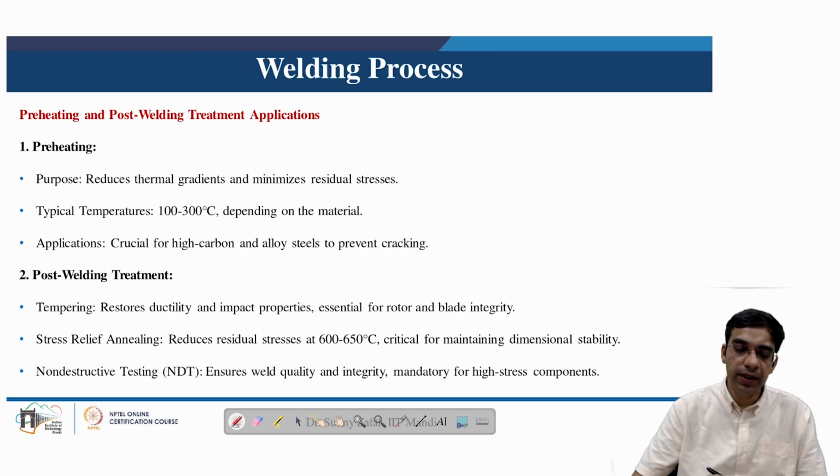And post-weld treatments are carried out because they restore ductility and impact properties essential for rotor and blade integrity. Stress relief annealing reduces residual stresses at 600 to 650 degrees Celsius, crucial for maintaining dimensional stability. Non-destructive testing ensures the weld quality integrity is maintained, which is very mandatory for high stress components.